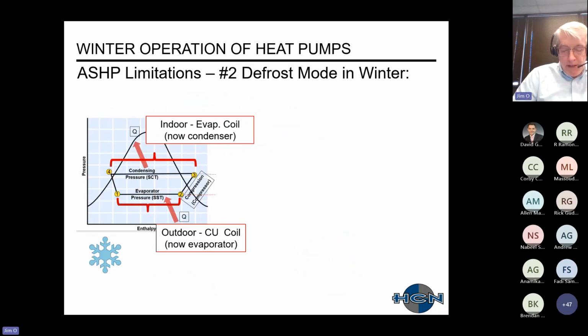Now, the other thing you have to be cognizant of with air source heat pumps is that they do contain a defrost mode, and this defrost mode will occur during the wintertime. On the left there just shows a P-H diagram for your refrigeration system. Want to make sure that you're understanding that in the heating mode, our outdoor condenser coil is now the evaporator, and our indoor evaporator coil is now the condenser. So as the Q, and the Q to me refers to energy, what we're doing is we're removing the heat from the outdoor air, dumping it into a refrigeration system, and then that refrigeration system is circulating, pumping with our compressor, et cetera, and then we're discharging the heat to the indoors.